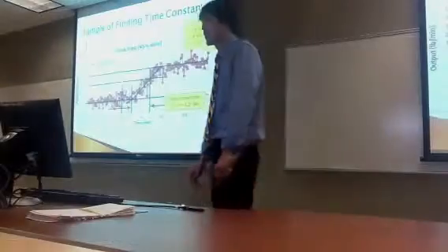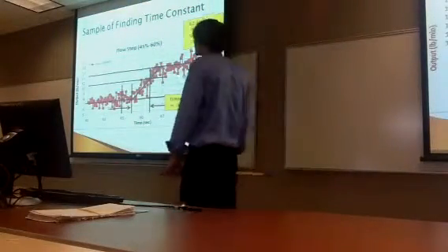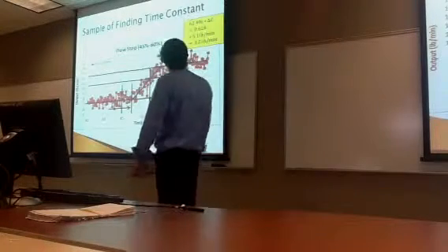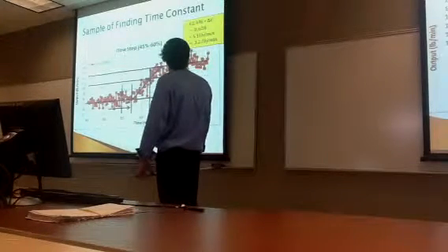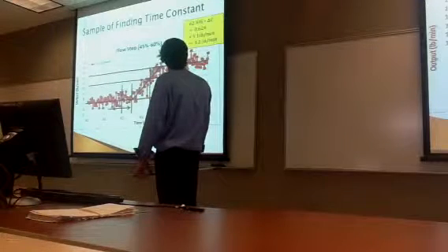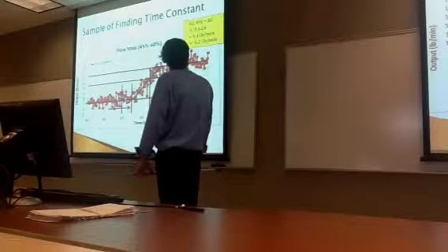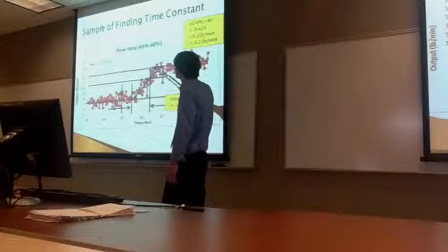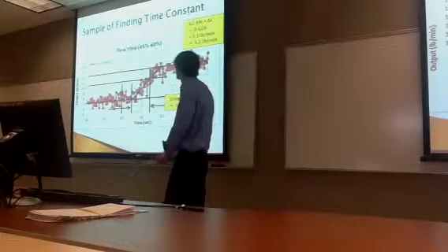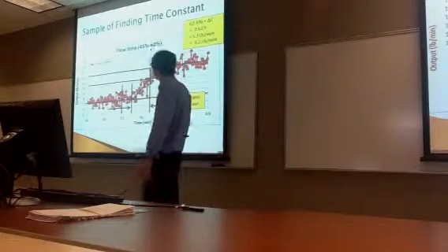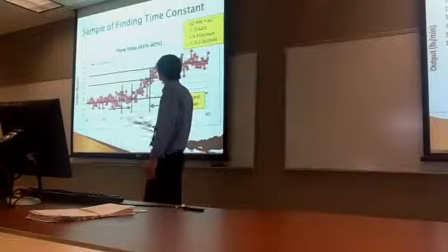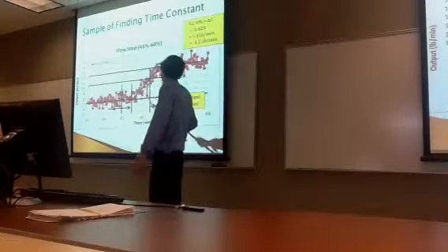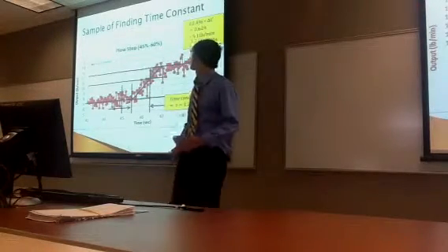Here's a sample of how we go about finding the time constant, using the FIT2 method. You take 62.3% of the change of the output, and in this case we found that to be 3.2. Then you add that to your lower value, and we found that it's about 10.5. Then from where the line intersects the step line, we find that the change from the end of the dead time to this point is the time constant. In this case, it's 1.2 seconds.